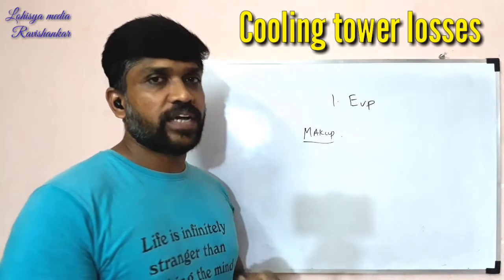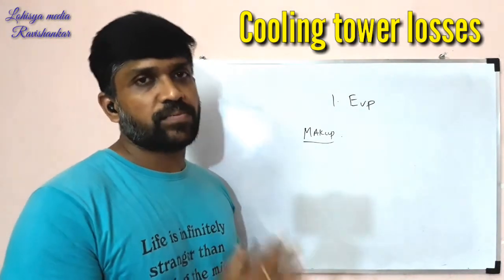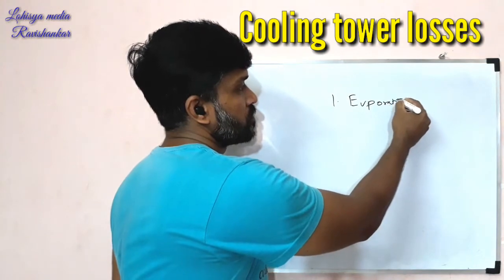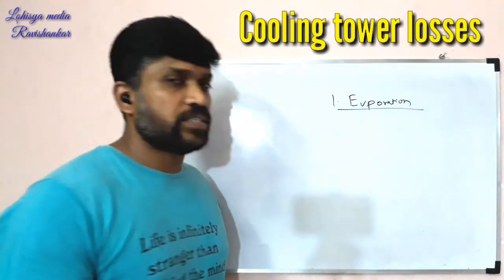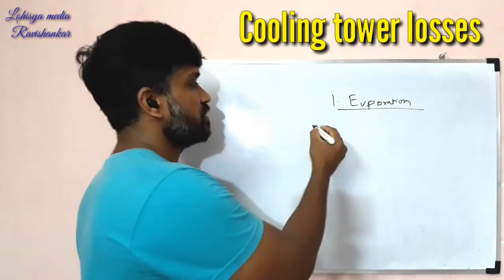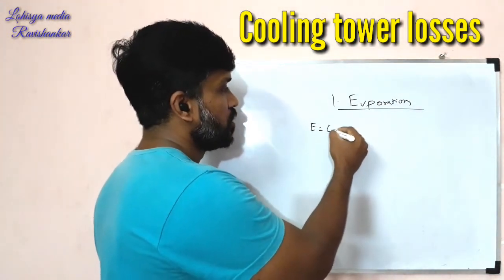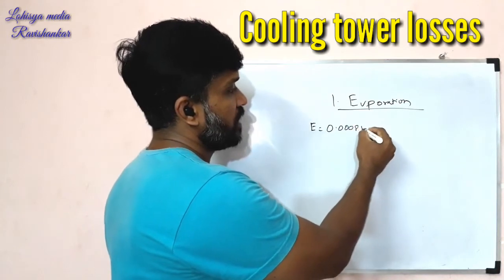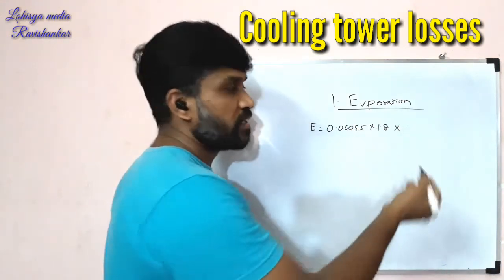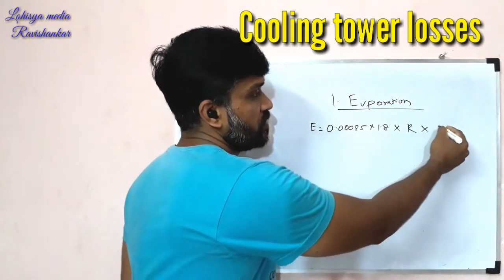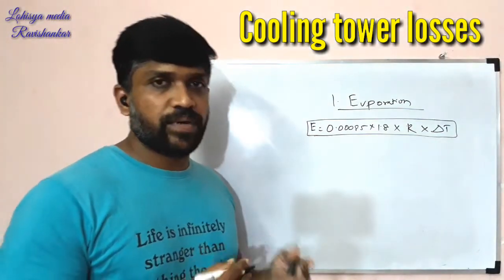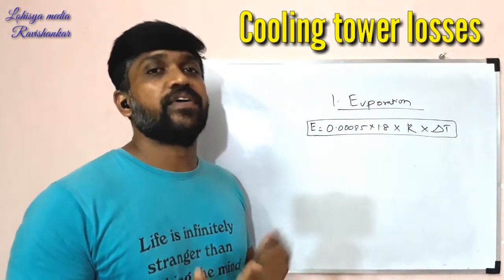First, we will calculate the evaporation process. We need to take the evaporation. The formula is: Evaporation = 0.00085 × 1.8 × hot water flow rate × delta T.